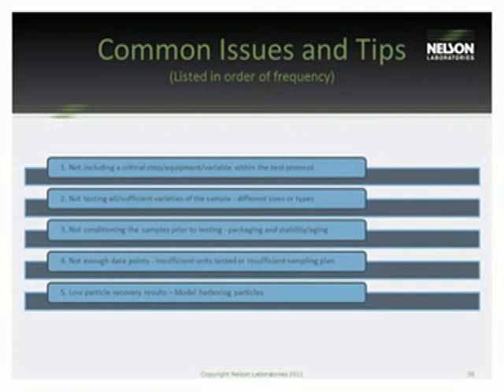Also, not enough data points, insufficient units tested, or an insufficient sampling plan. I said earlier you don't necessarily have to have a ton of units, but you should have a good amount. I wouldn't submit 3 units to regulatory, 3 points of data, and expect it to fly. You're probably going to want 5 or 10 or 20. It's a sufficient amount, a good statistical number. And most sampling plans at most major manufacturers are pretty good, so that hasn't typically been a problem, but that's why it's number 4.